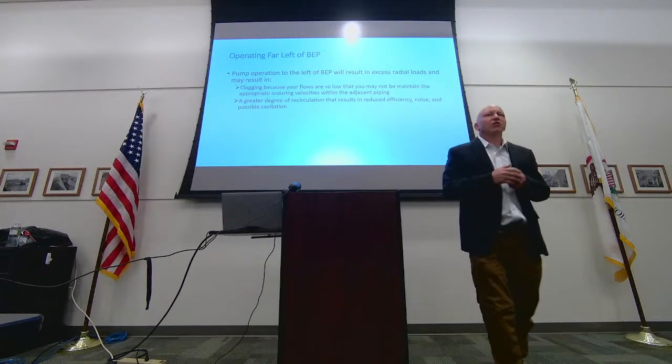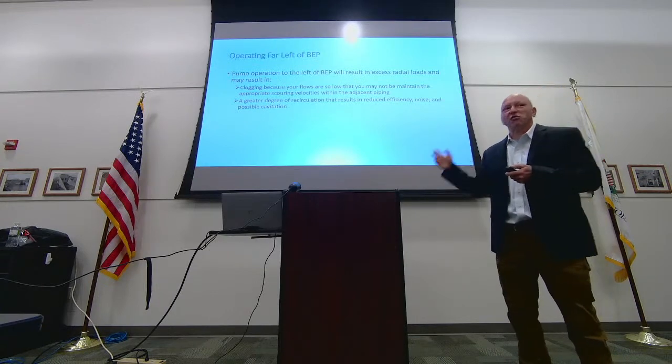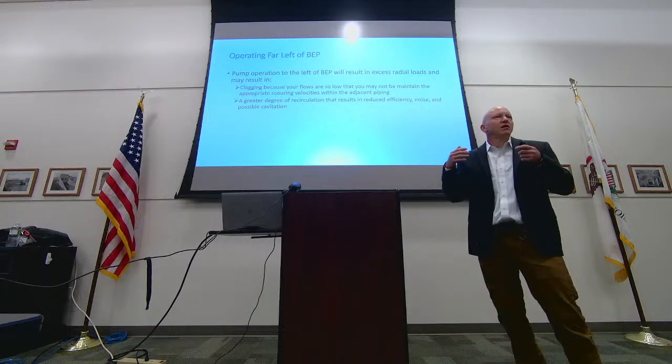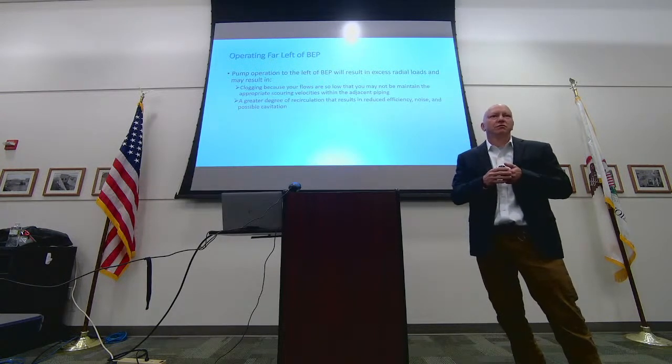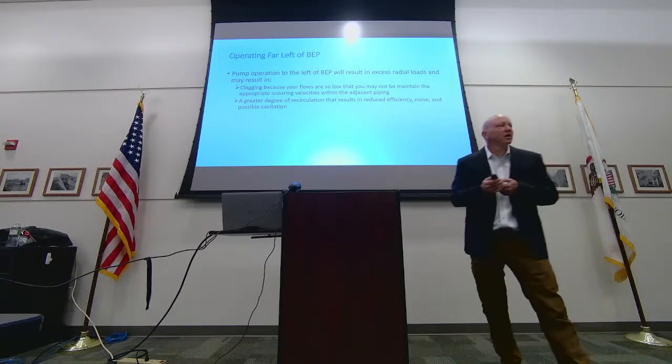Does anybody know, and there's another formula that I won't put up there, but what is the basic scouring velocity of wastewater pipe? Anybody know? 2 feet per second, right? Yep, 2 to 2.5 feet a second.